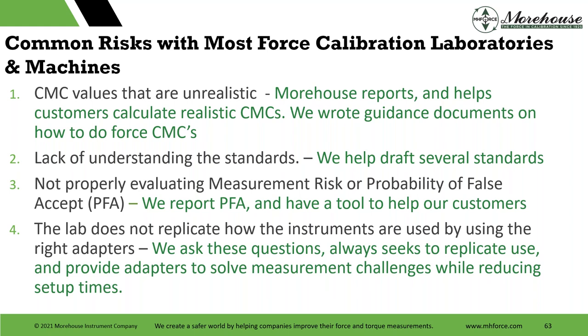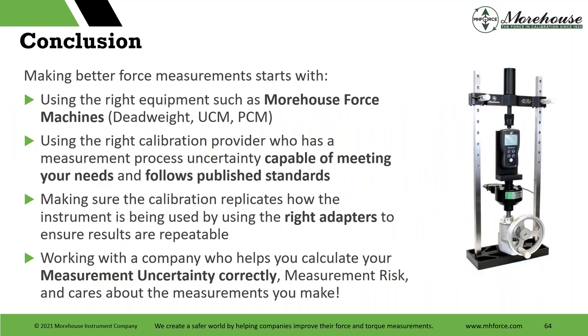And more so than anything, the lab does not replicate how instruments are used by using the right adapters. You saw the errors in this presentation. Even if you do purchase a Cal machine or you do purchase an automation upgrade, if you're not using the right adapters, your error sources can be super large, as a 0.3 with the top block, over 1% with the wrong pin on the tension links. 0.12, that's not a super large error for most people, but 0.12 from loading against the base versus not. And there are more and more of those adapters, overshooting test points, lots of other things in there as well.